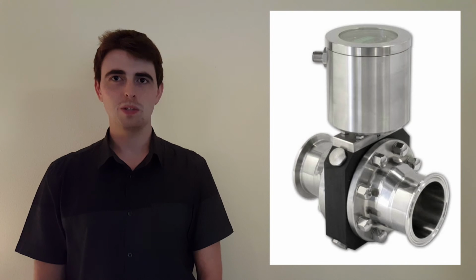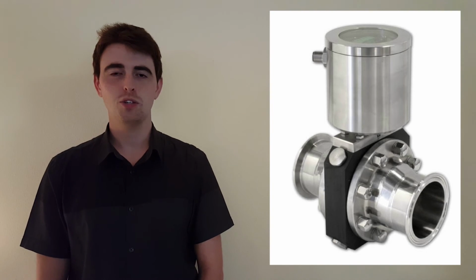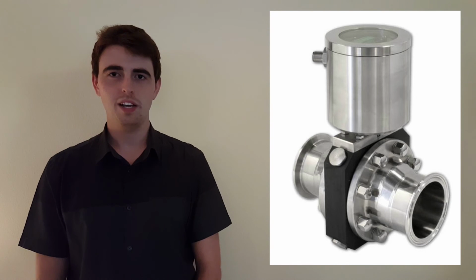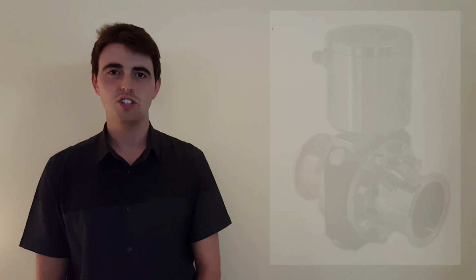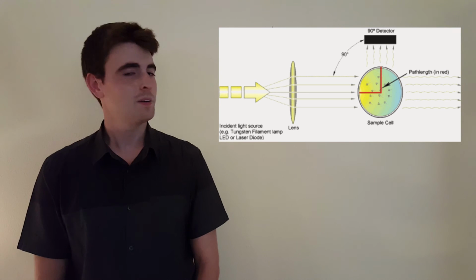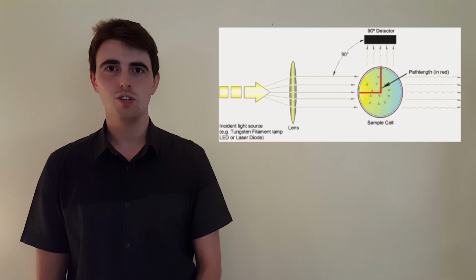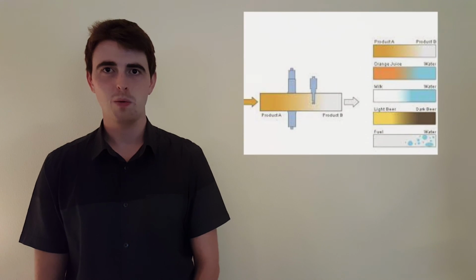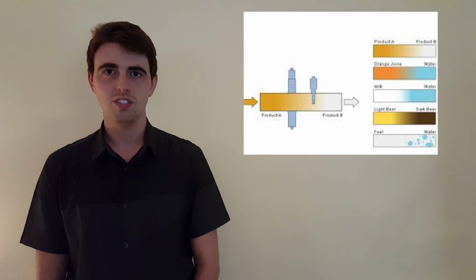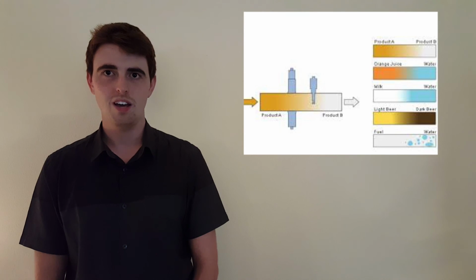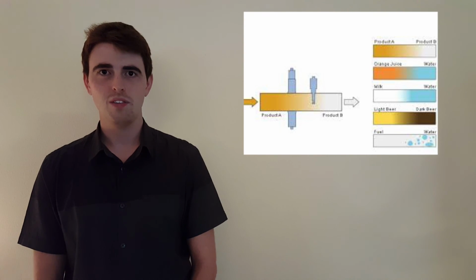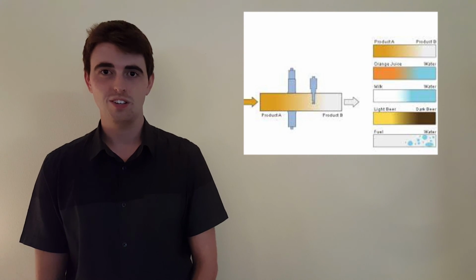A turbidity meter was determined to be the optimal solution for this project. A turbidity meter shoots a beam of light into a liquid and the amount of scattered light is measured to determine the density, as shown here. As soon as the density transitions from water to product, the valve will switch and the good product will not be wasted. Using this method instead of a 330-second set time will also achieve annual savings in excess of $100,000.